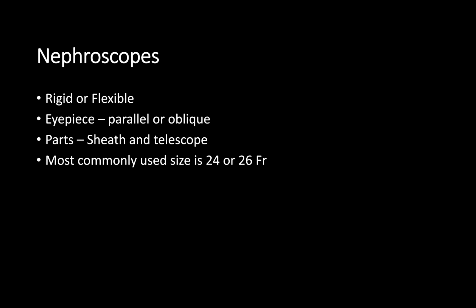Explain the nephroscope, how it is made. So a nephroscope consists of the eyepiece, a light post, and the light lead, and a handle. In terms of the working element, it has a semicircular configuration, which is open on the superior aspect, and this allows it to be accommodated within the Amplatz sheath. The length of the working element is approximately 15 to 20 centimeters, and light transmission works on the basis of fiber optics.